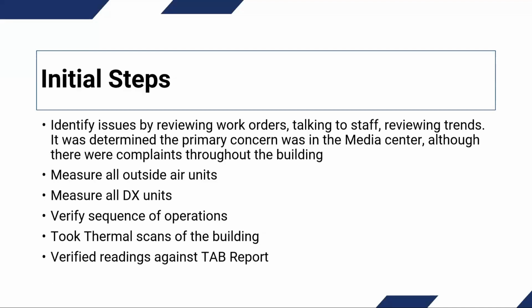On projects where we have an issue and we did the test and balance, we do verify. We do go back to the test and balance report. We never send the same crew. We send another crew out and we verify the readings that we're taking during the troubleshooting procedure against the readings that were on the test and balance report. We do this for quality control. We do it to see what, if anything, has changed between our initial readings and our final readings. But when we do the test and balance and we have a problem, we do go back and verify against the TAB report, which is something that we do not do if we did not do the test and balance.